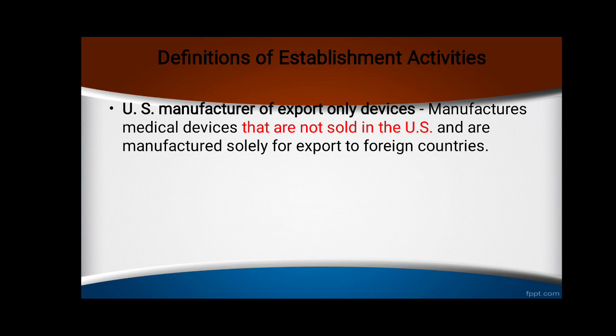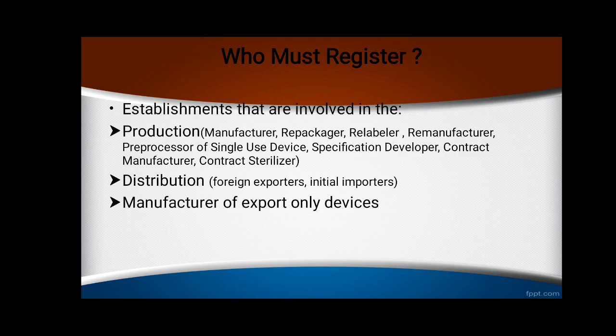A U.S. manufacturer of export-only devices manufactures medical devices that aren't sold in the U.S. and are manufactured solely for export to foreign countries. Well, after you have familiarized yourself with the types of these establishments based on FDA definitions, now it's time to answer this question: who must register?